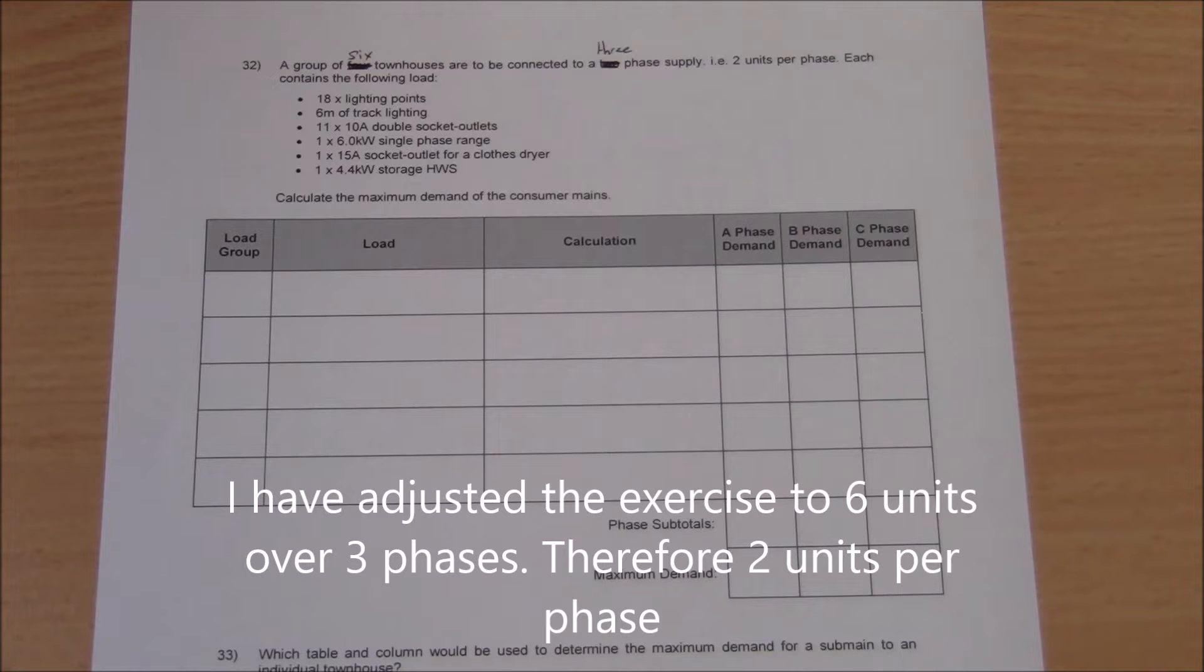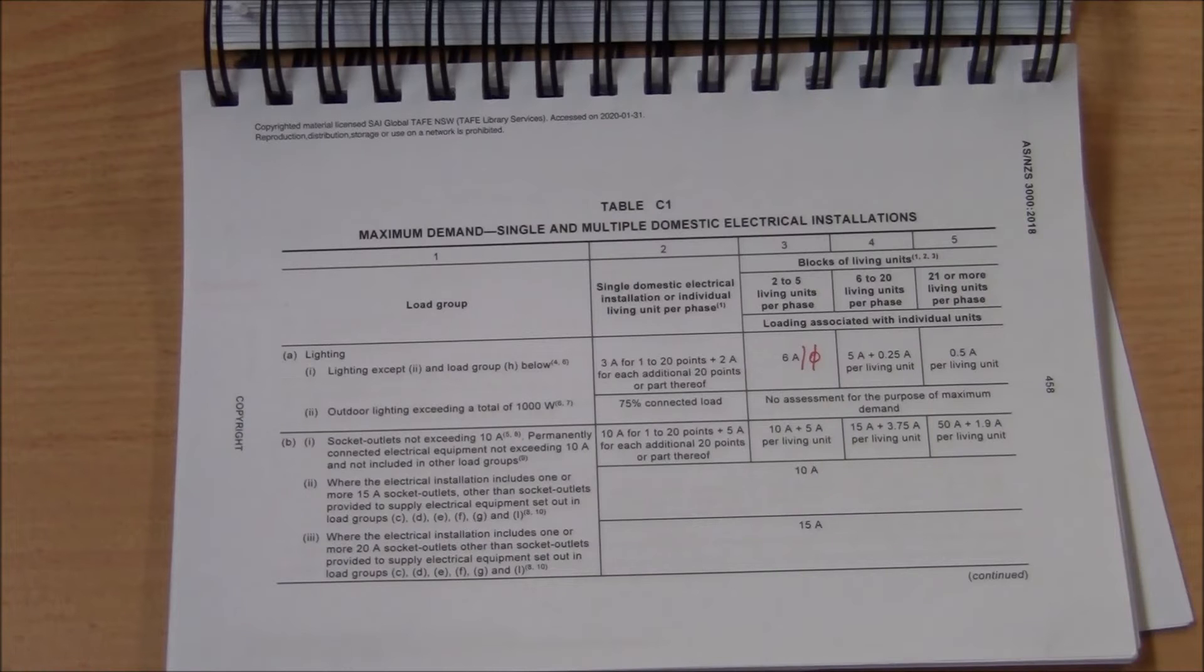Page 83 of your workbook has a maximum demand exercise. To complete this exercise revolves around a multiple domestic installation. This installation is for two units per phase. Let's consult table C1. As it's a domestic installation, columns 3, 4, and 5 relate specifically to blocks of living units. This exercise is for an installation with two units per phase, so we will concentrate on column 3.